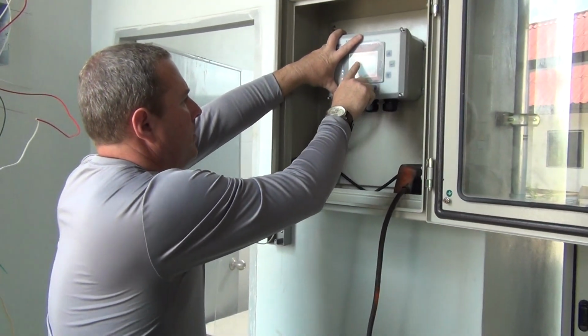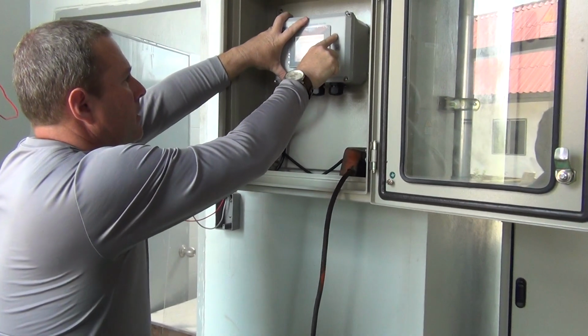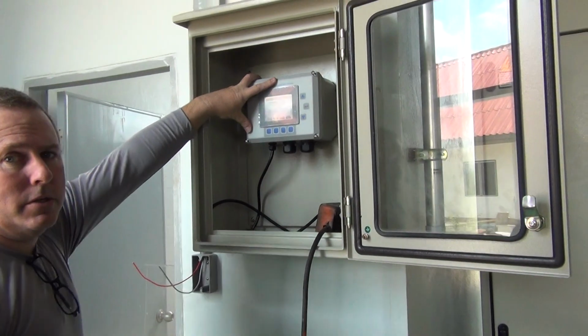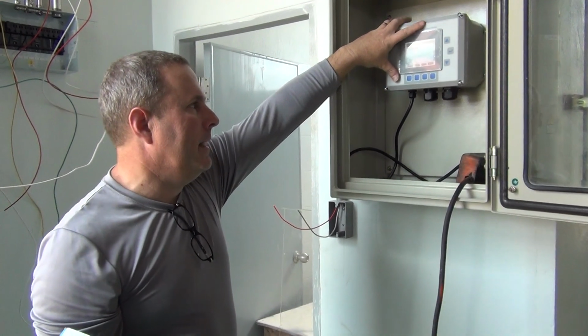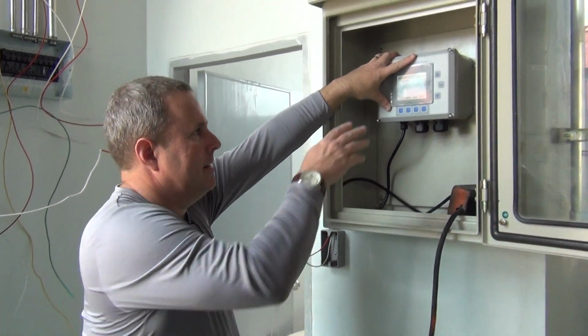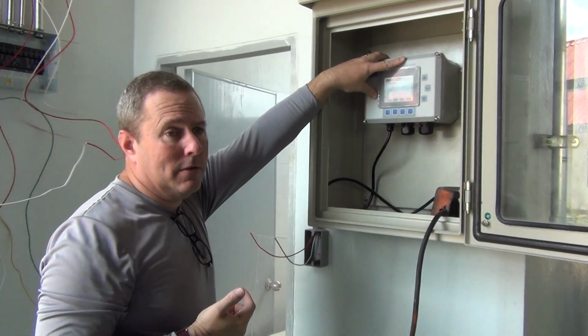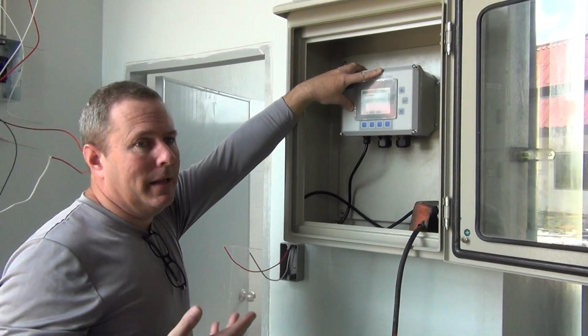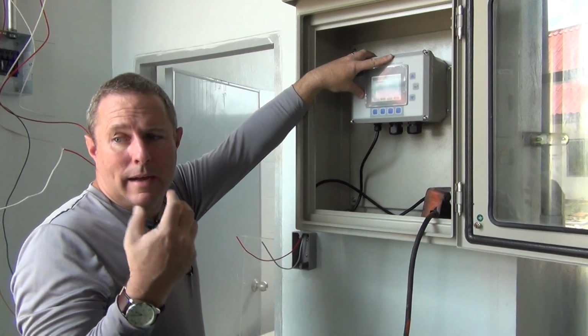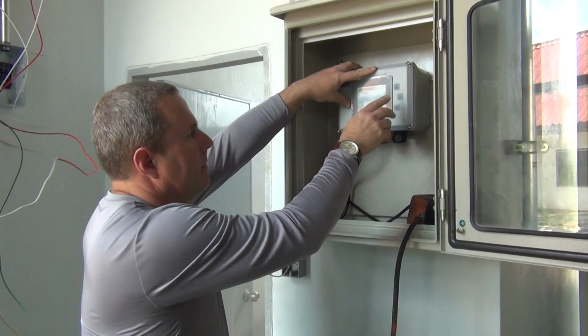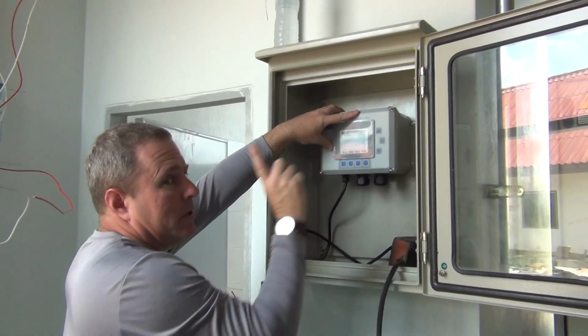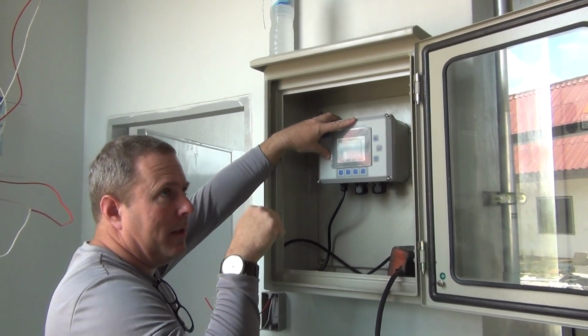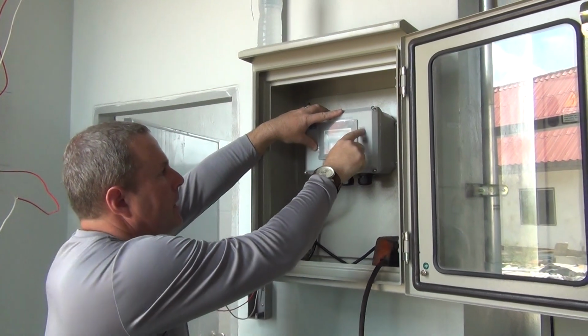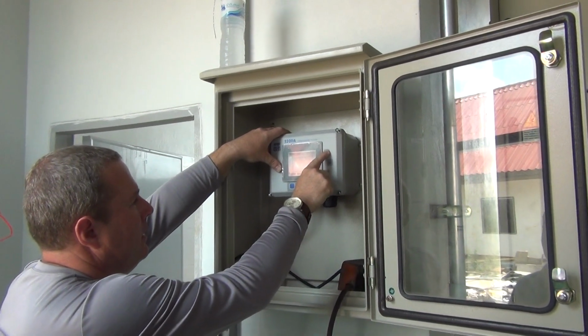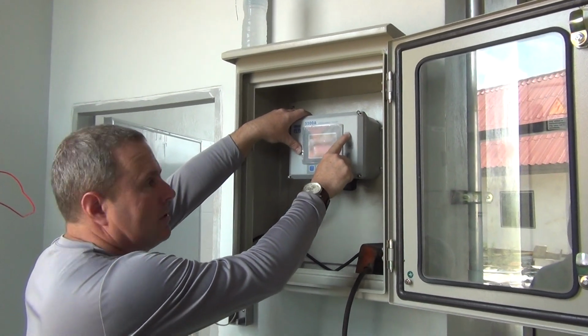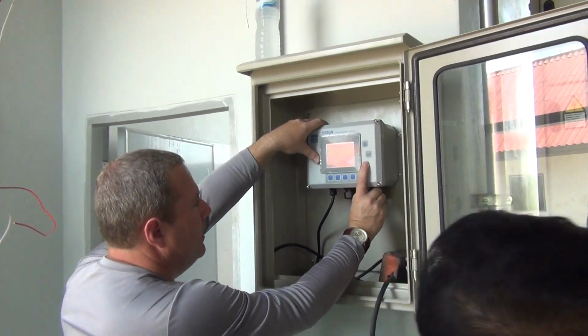Now, let me tell you a little bit about what each function under the menu does. The one that you'll probably use the most is adjust contrast. This is a product that has been around for a long time. They started with LCD screens, and because this product has been in production for 14 years, they haven't updated to the latest technology. So LCD, when it gets hot or cold, obviously the temperature change influences how you can see it. So you can press adjust contrast, which is always the first choice if there's a power outage. You can know that you go down X number in case you can't see the screen clearly, because what can happen is if the contrast is off, it can look like this. If it's too hot, it can be very difficult to read. Or if it's too cold, it would be to the other extreme.